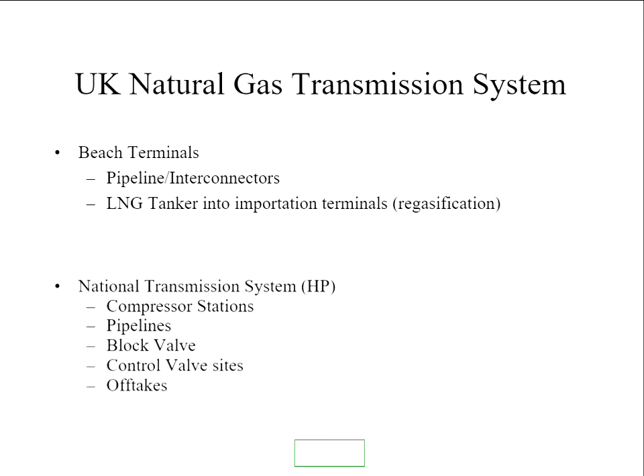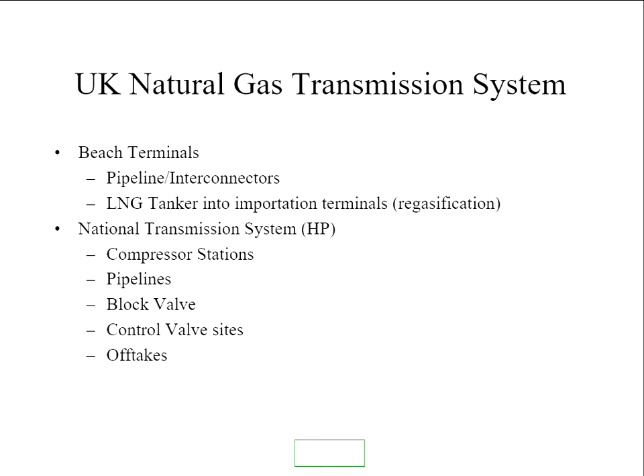Sure. Yeah. So then we've got the national transmission system, which is a high pressure system, sort of components. We've got compression, which I suspect has been rather heavily used this winter because there's been a lot more gas coming back into Scotland. A lot of pipelines, MOP ratings anywhere up to 94 bar, but historically it was 70 bar, but it's crept, so you've got 75 bar, 84 bar, 85 bar, 94 bar. Block valves so they can isolate. Control valve sites so you can actually manage and control flow. And offtakes where the various next stage consumption of gas takes place.